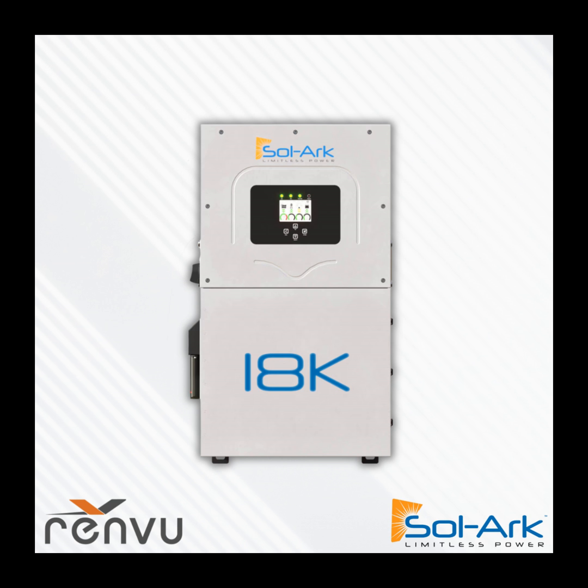For off-grid systems too, it's just keep adding more batteries, because with two battery ports, and given that these monolithic batteries typically come with either integrated busing systems or an adequate number of ports for wiring - what I mean is the Discover Helios battery doesn't include an integrated bus bar, but it has 4 battery ports. That means you can wire 3 of them together in parallel just using the wires that come with it, then click it into a single battery port on the Sol-Ark. So it's very easy to design with.